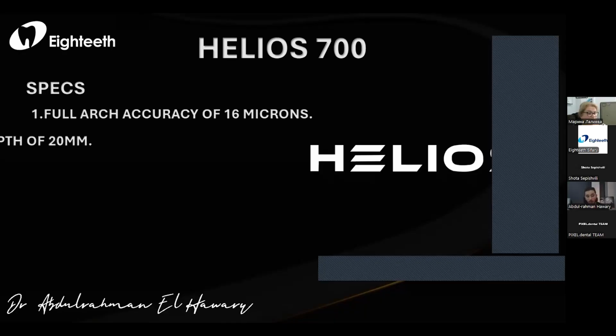Second thing is the scanning depth. We do have a scanning depth of 20 millimeters. And let me clarify here that Eighteeth is one of the few companies that actually put the true scanning depth inside their catalogs, because there's false marketing going on in the market right now, with other companies calculating the scanning depth in the wrong way. The correct and most honest way is to calculate it from outside of the tip of your scanner. So when we calculate the scanning depth from outside of the tip of the Helios 700, it's 20 millimeters.